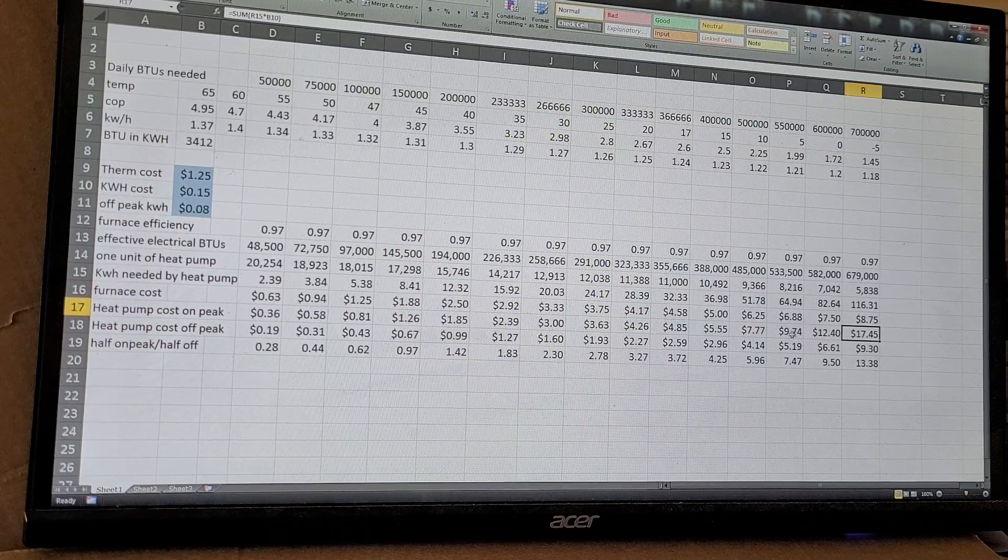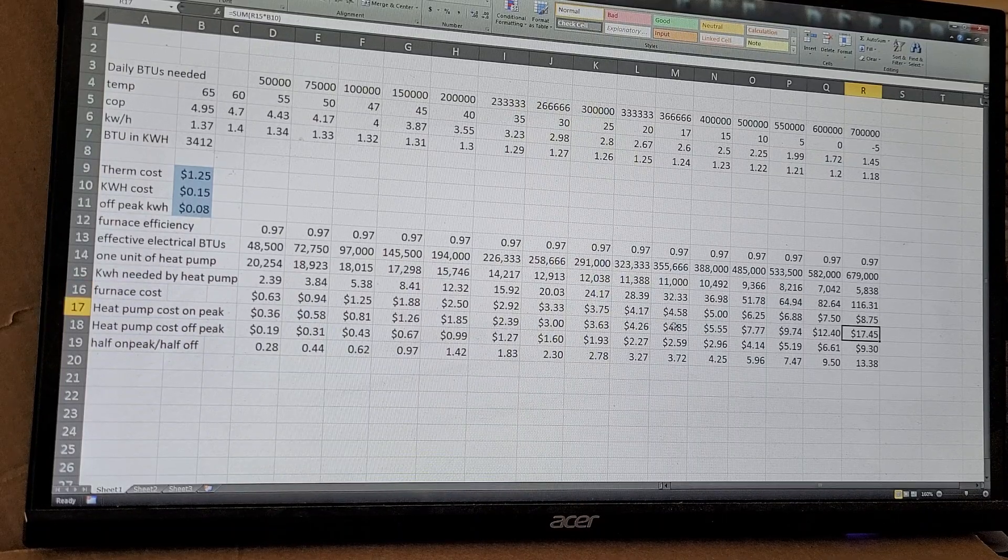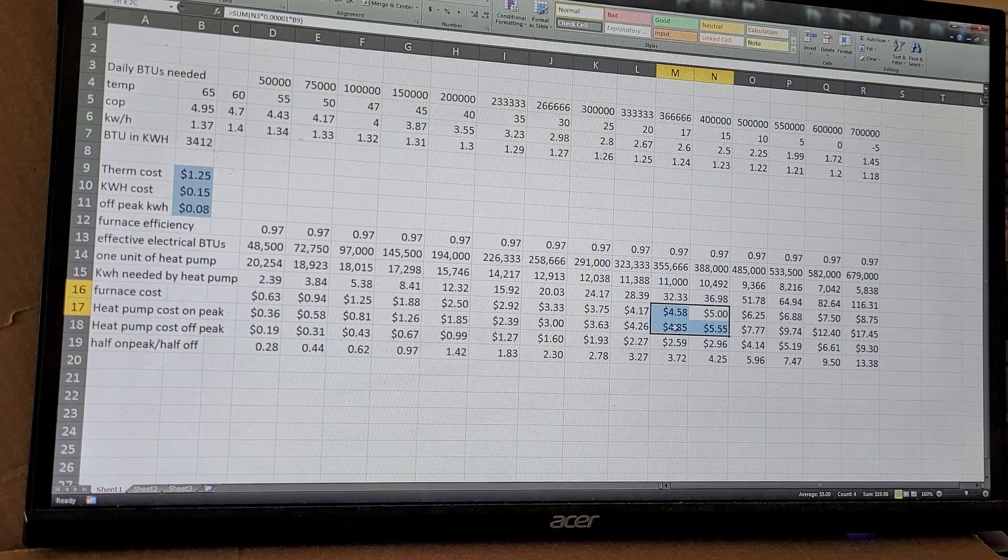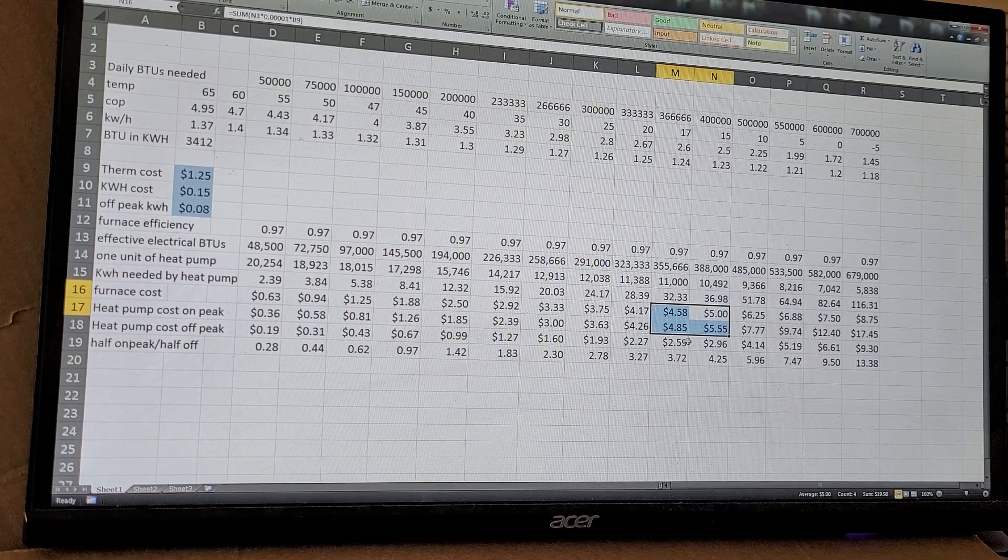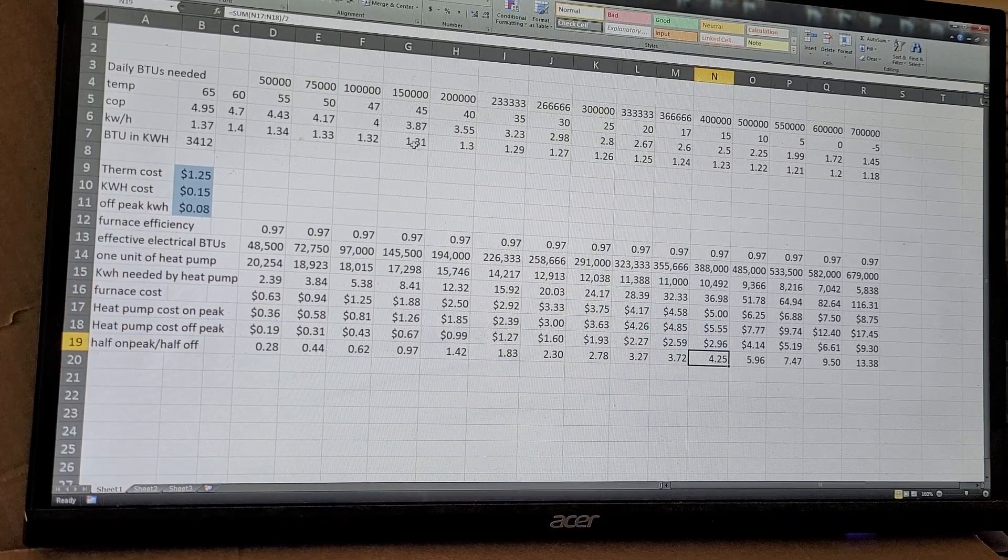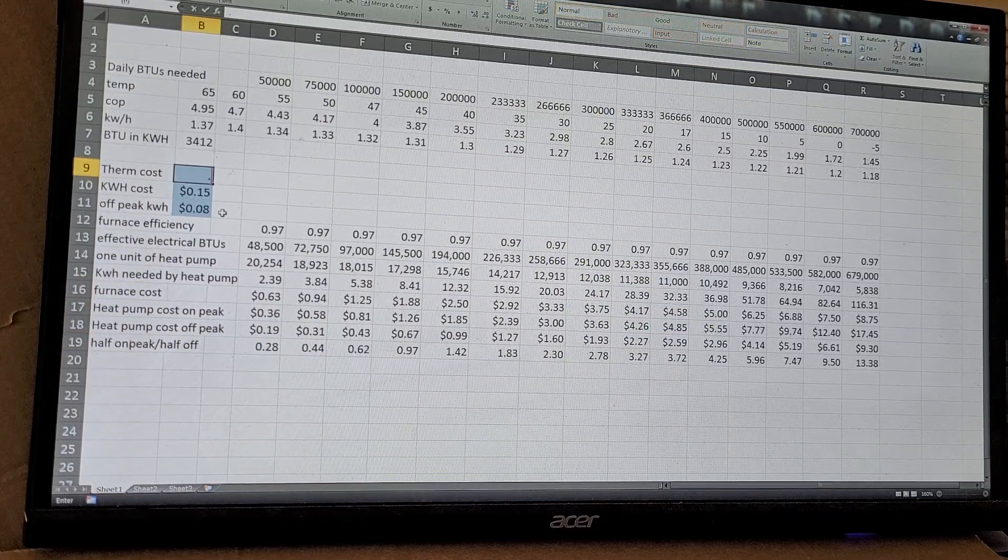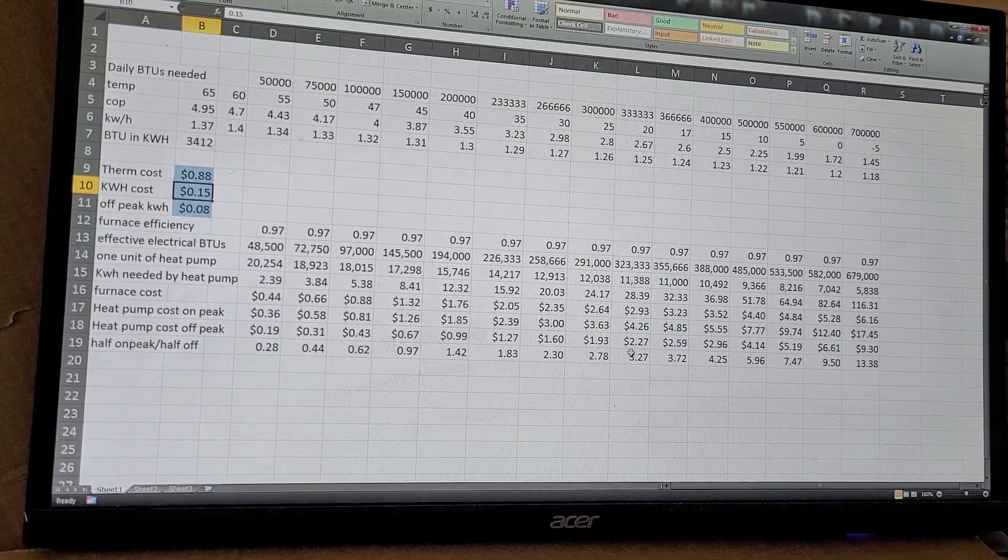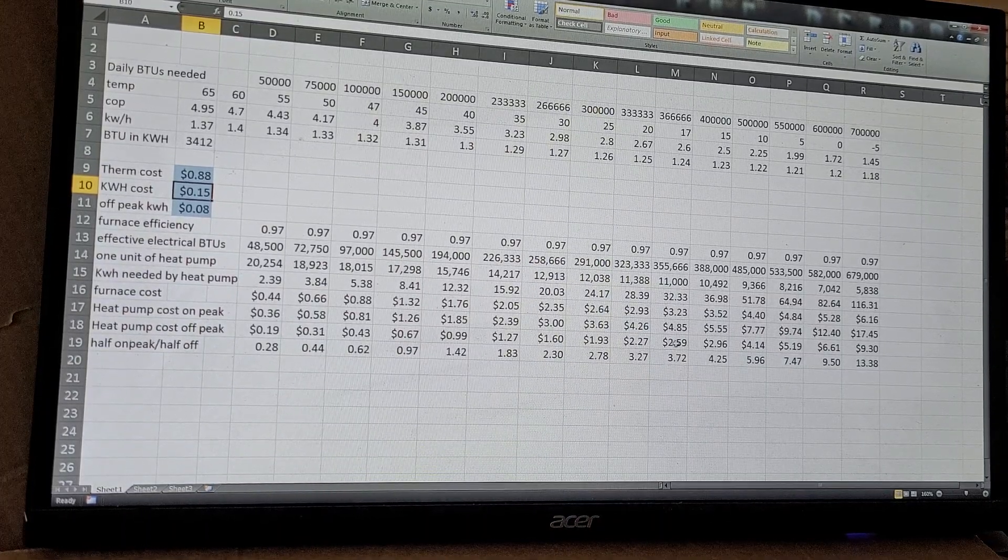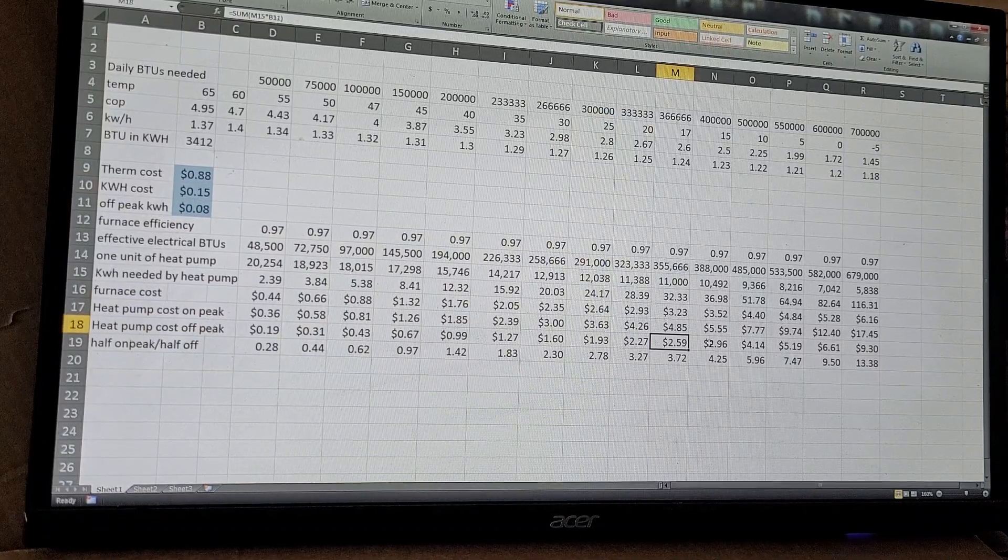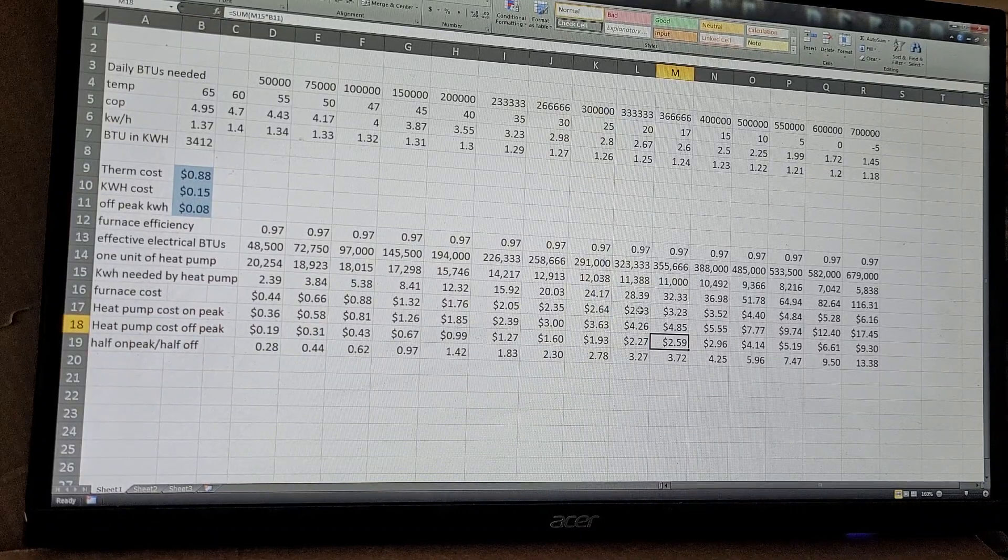But if you're paying on-peak rates for electric, well that number changes a lot differently here. Somewhere between about 16 degrees, that's where you're going to see the change about which is going to be more expensive for the heat pump. Even if you're paying about 88 cents a therm on your gas, that means that I'm probably going to be running the heat pump when it's over about 20 degrees.